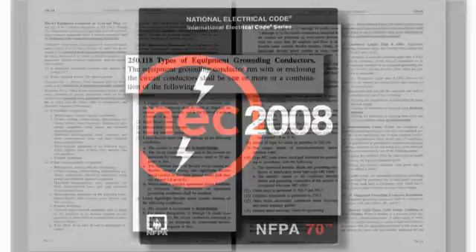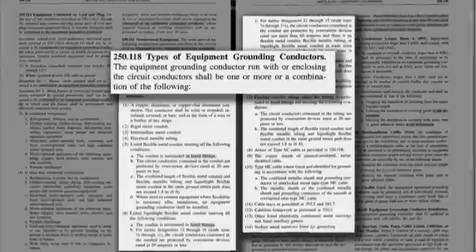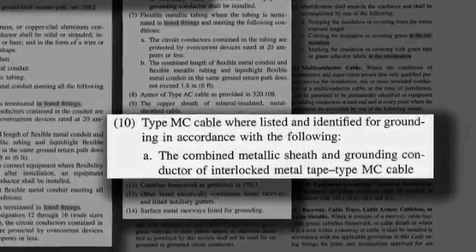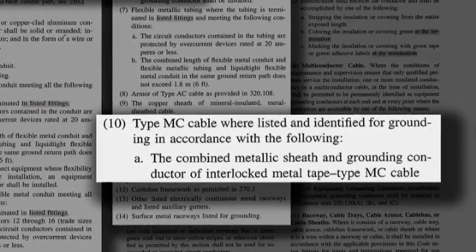NEC Section 250.118 lists the types of acceptable equipment grounding conductors. Item 10A, covering interlocked armor MC cable, states that the combined metallic sheath and grounding conductors form the ground path for the cable.